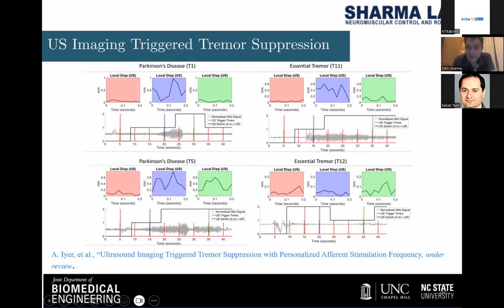So now the ultrasound has triggered the stimulation, and the moment the stimulation is turned on, the tremor is suppressed. At the same time, the ultrasound is not affected by stimulation artifacts, so we can take measurements anytime without stopping the stimulation. But since the tremor has been suppressed, now we turn off the stimulation. We have shown this on multiple patients. If the tremor is suppressed, we don't need stimulation. If the tremor comes back, for example in the fourth patient at the bottom here, we turn the stimulation back on.